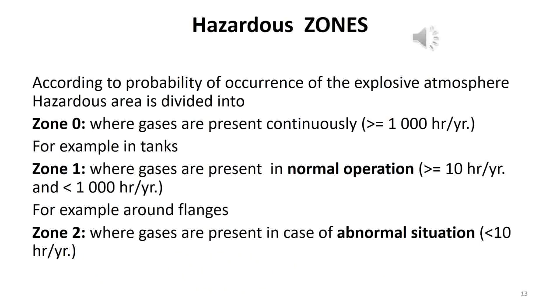According to probability of occurrence of the explosive atmosphere, hazardous area is divided into Zone 0, where gases are present continuously, more than 1,000 hours per year, for example in tanks. Zone 1, where gases are present in normal operation, between 10 and 1,000 hours per year, for example around flanges. And Zone 2, where gases are present in case of abnormal situation, less than 10 hours per year.